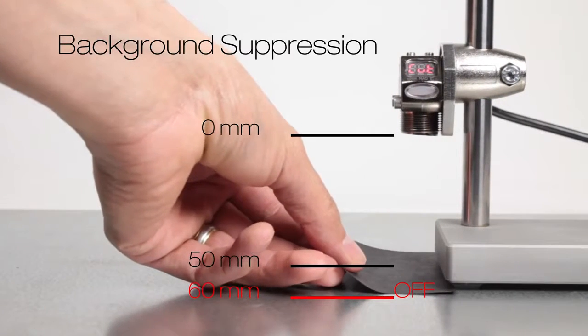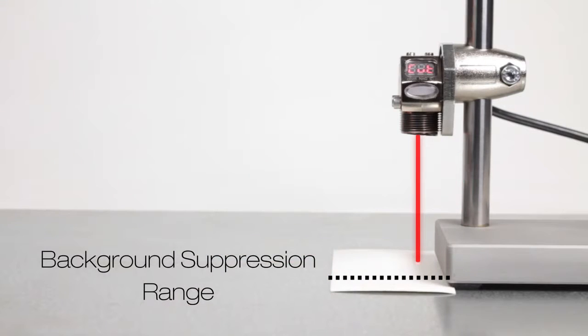The Q3X has background suppression capability so it ignores targets of all colors and reflectivities outside its 60mm background suppression distance.